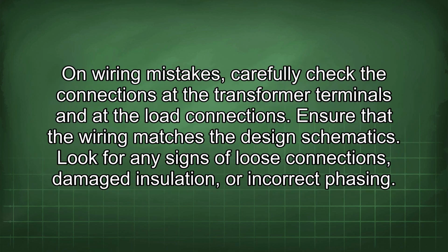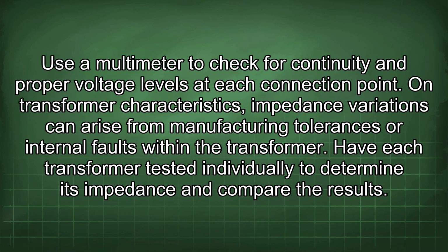On wiring mistakes, carefully check the connections at the transformer terminals and at the load connections. Ensure that the wiring matches the design schematics. Look for any signs of loose connections, damaged insulation, or incorrect phasing. Use a multimeter to check for continuity and proper voltage levels at each connection point.